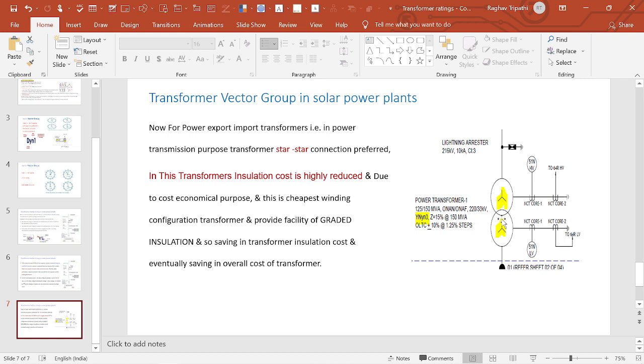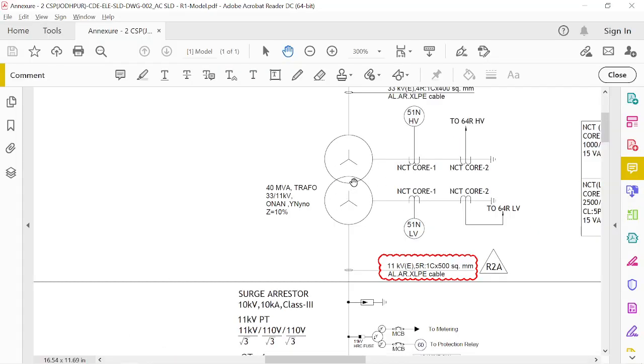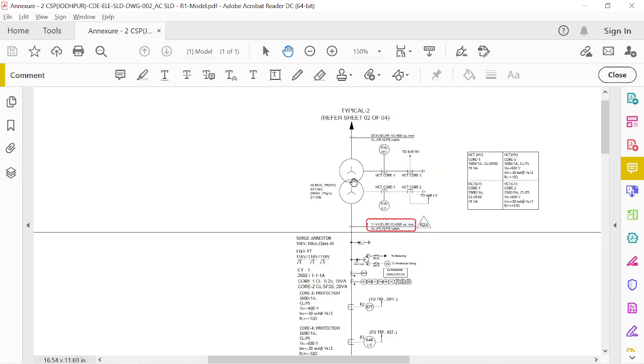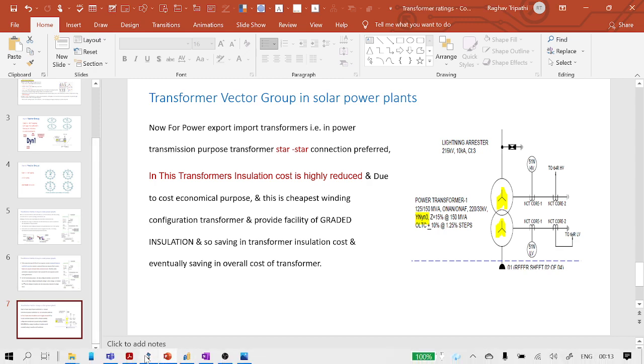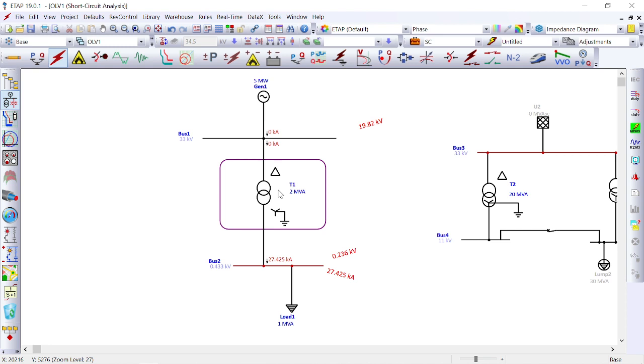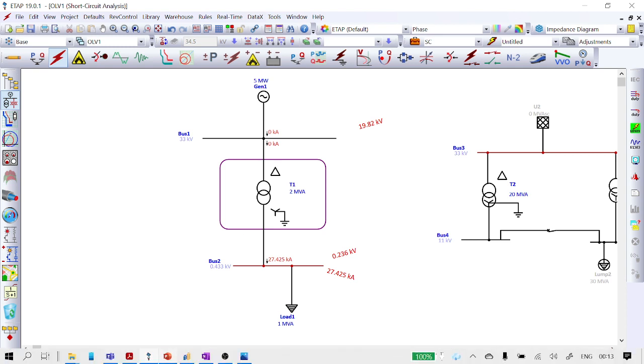We go with star-star due to it being the cheapest winding configuration. Additionally, with star-star we can have graded insulation in the transformer, providing savings in transformer insulation cost and eventually overall transformer cost. That is why the power transformer is selected with the star-star vector group. For the auxiliary transformer, DYN11 is used as usual. This is the reason for selecting delta-star or star-star vector group configurations for the respective transformers in a solar power plant.